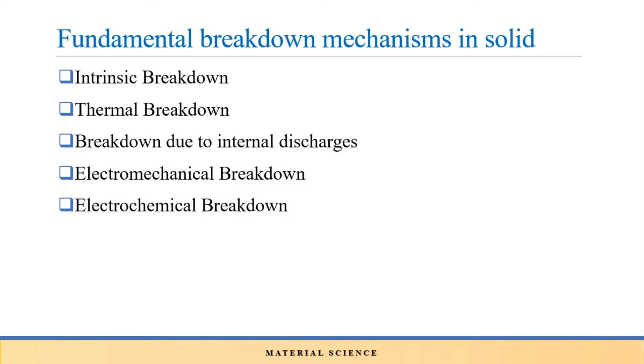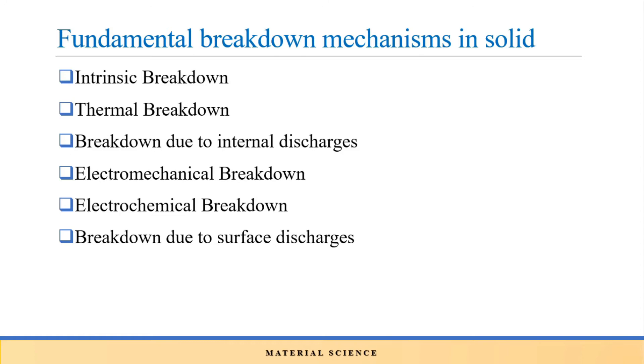If there is presence of some chemicals in an insulating material, they are responsible for the transfer of electrons — such breakdown is known as electrochemical breakdown. Next is breakdown due to surface discharge: if there is moisture or dust content on the surface of the insulating material, it allows the electric field to pass through, contributing to breakdown of the insulating material.